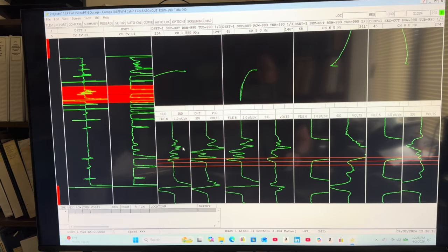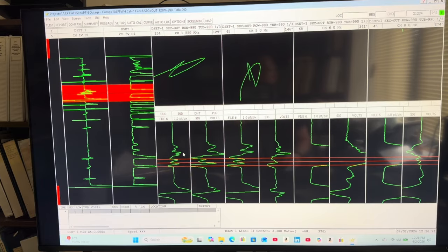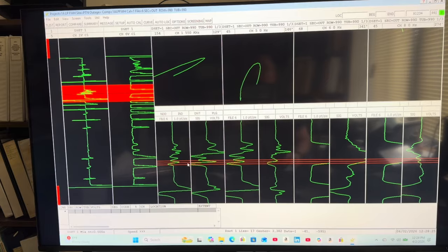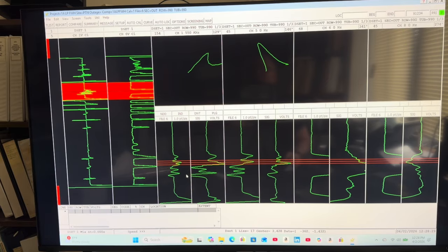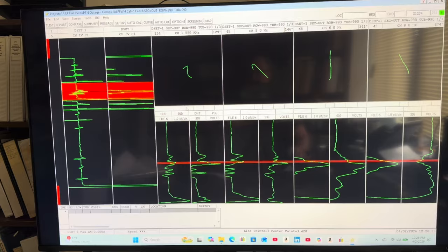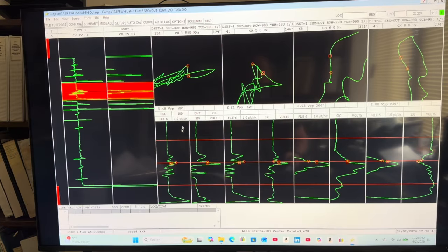So as I scroll through this data, there's probably one flaw, there's another flaw right in the middle there. So you got 1, 2, 3, 4 maybe. You got one that's real deep in there. See that right there? That little vertical spot. That's probably the deepest area in this whole little cal tube here. That's probably 60 or 80% deep.